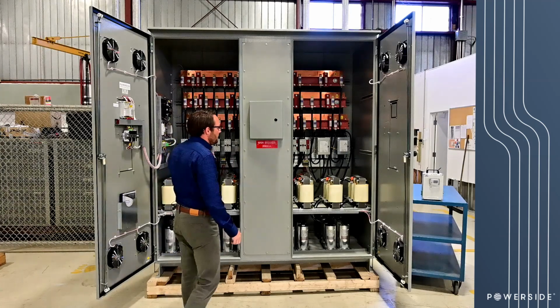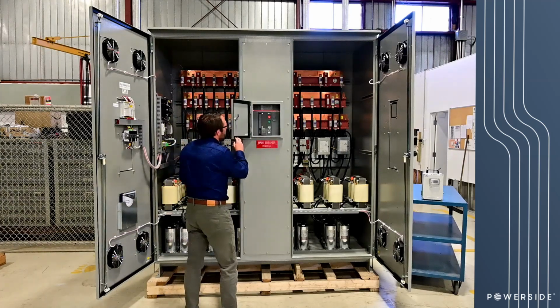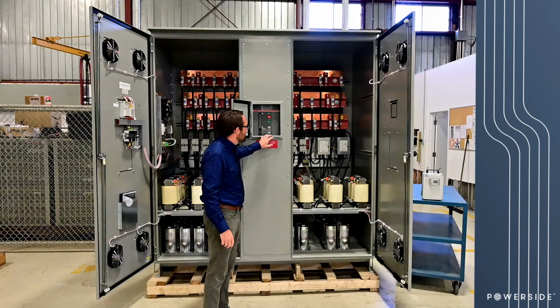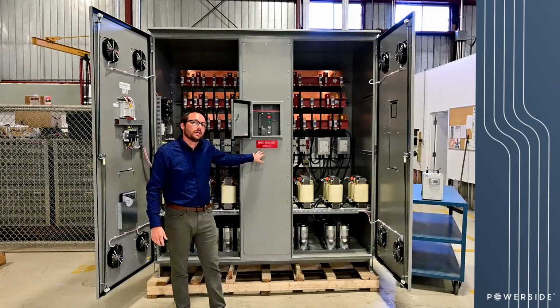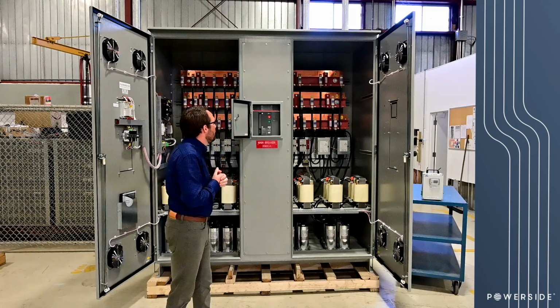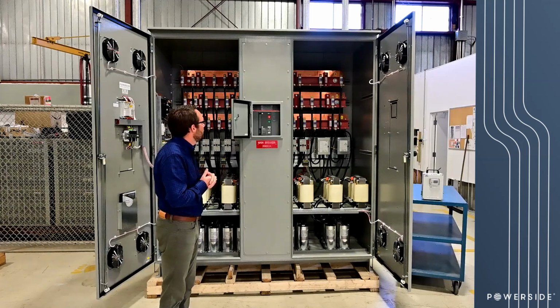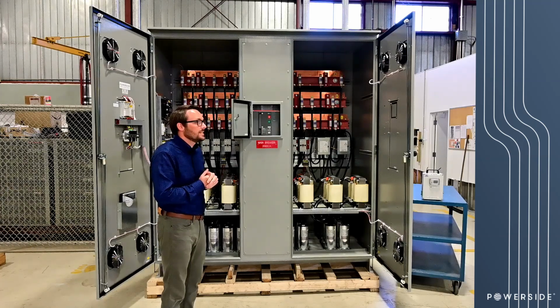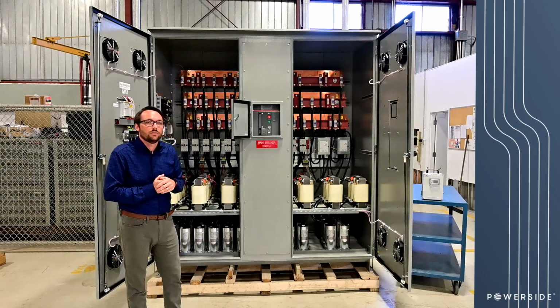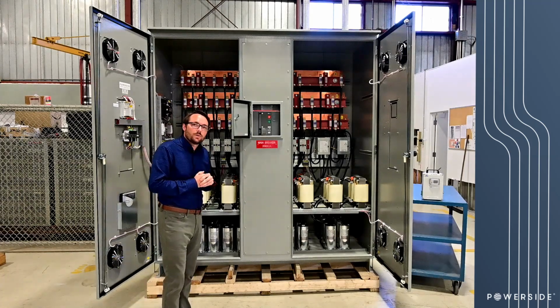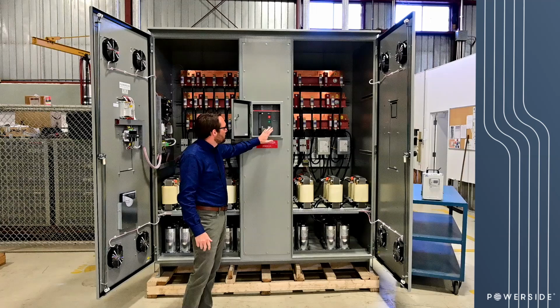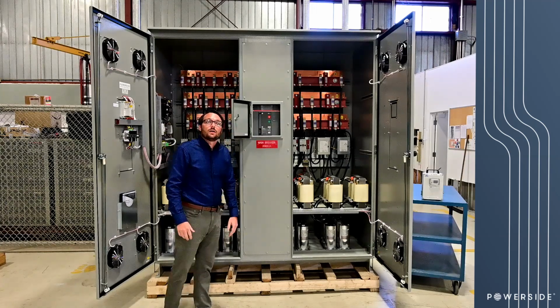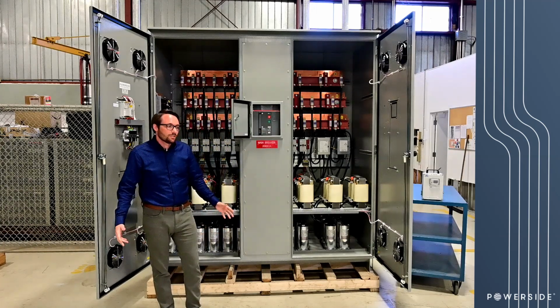And then one of the other things to note about this system is that this is coupled with a main breaker. So this is a 2000 amp ACB breaker, which the client is using what I believe to be known as the tap rule in the NEC code. So they're coming right off of the main bus bar of the switchgear directly into the main breaker, and then our equipment would operate as such.